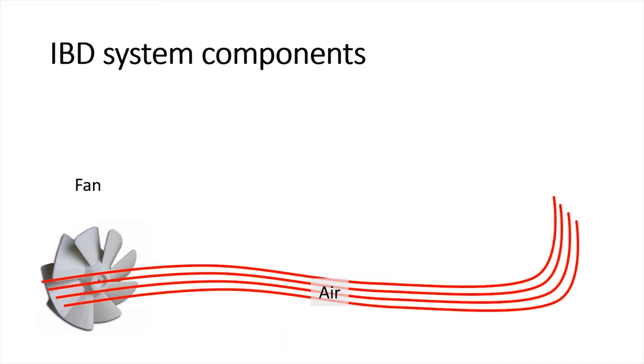The second component is the fan. Historically the fan has been the only thing farmers have addressed — the common thought is to upsize the fan to get more airflow. Unfortunately, that isn't always the case. Every fan is dependent on back pressure, and back pressure has far more to say about airflow than fan design. There are certain instances where upsizing from a 5 to a 7 horsepower will get you more airflow, but in many cases that just wastes your money. It's really important to understand the downstream components before spending money on fans. Axial and high-speed centrifugal fans can only handle very low static pressures and we typically avoid them for in-bin drying.